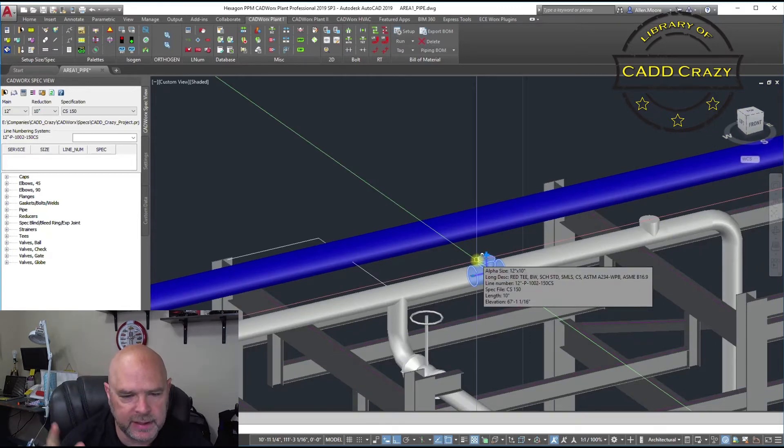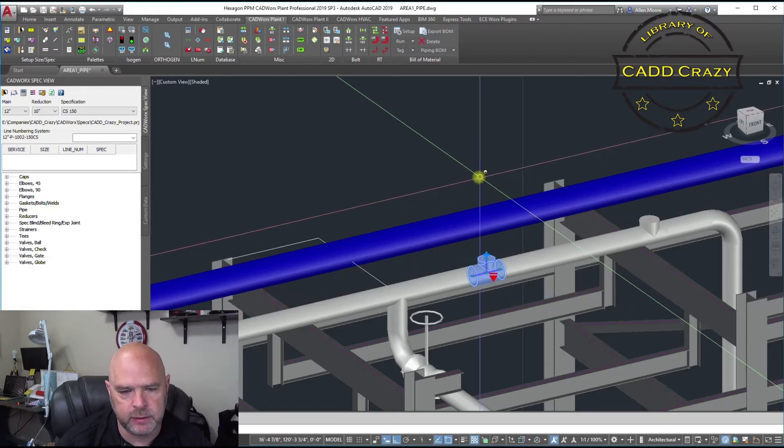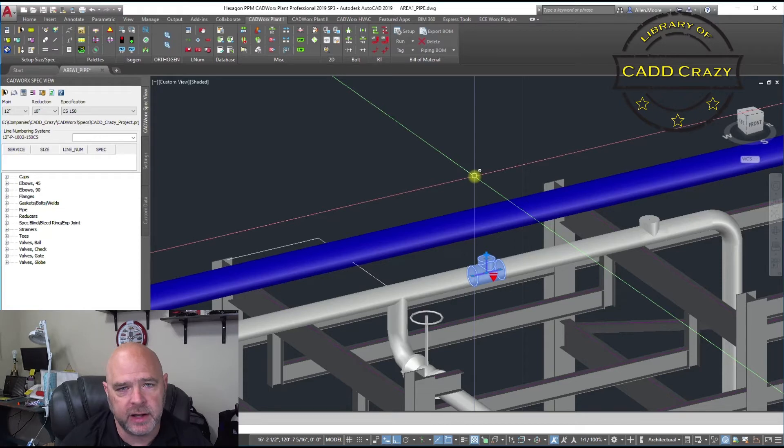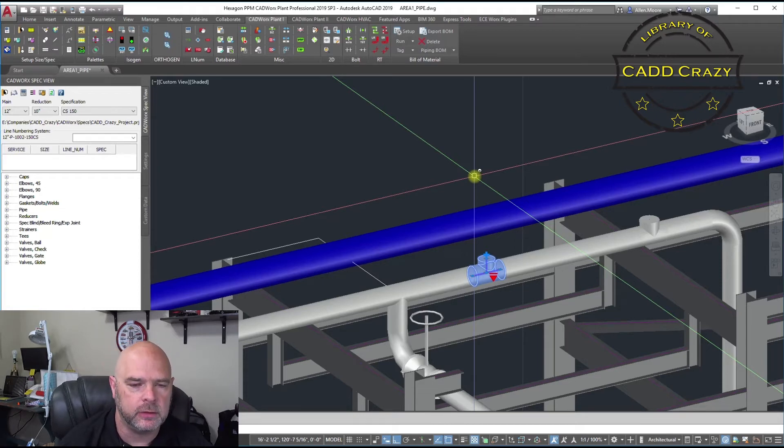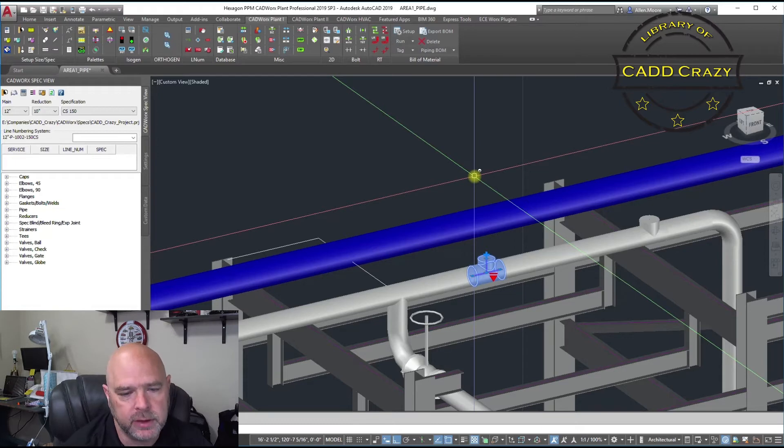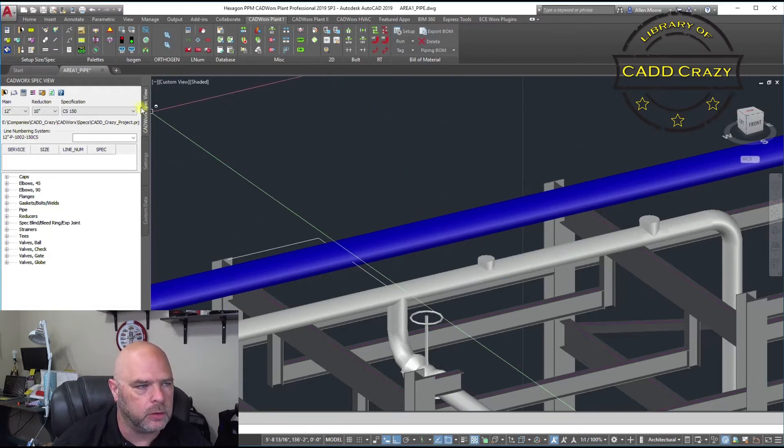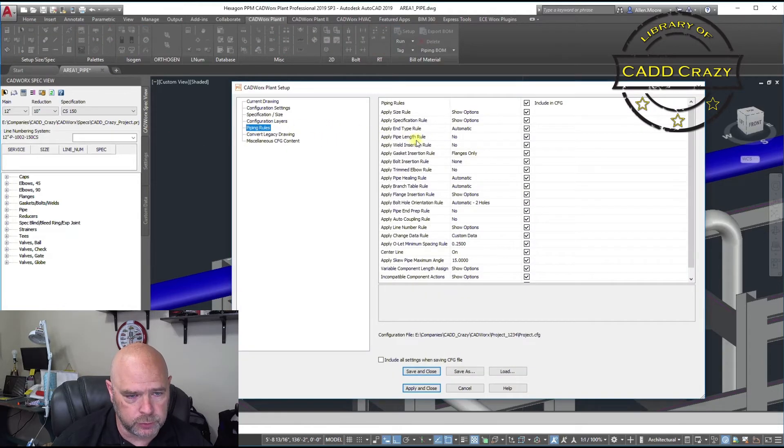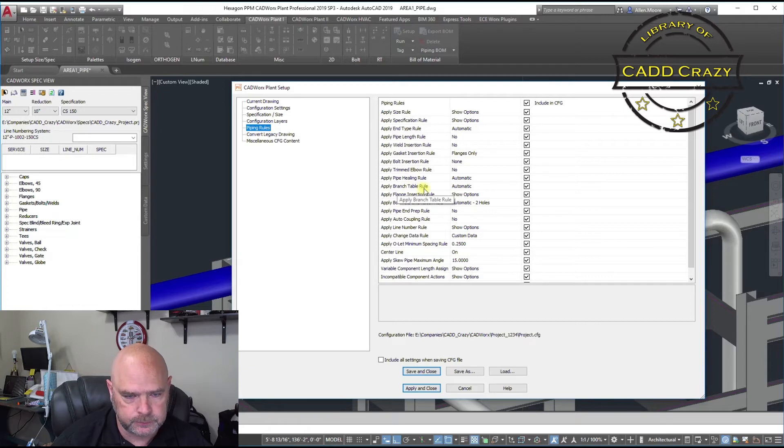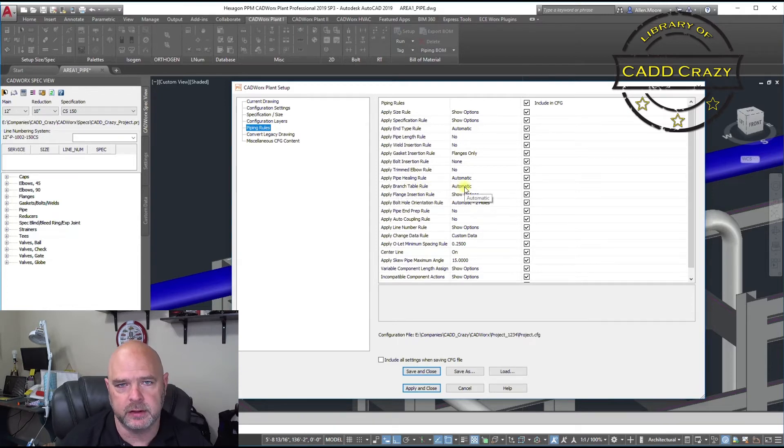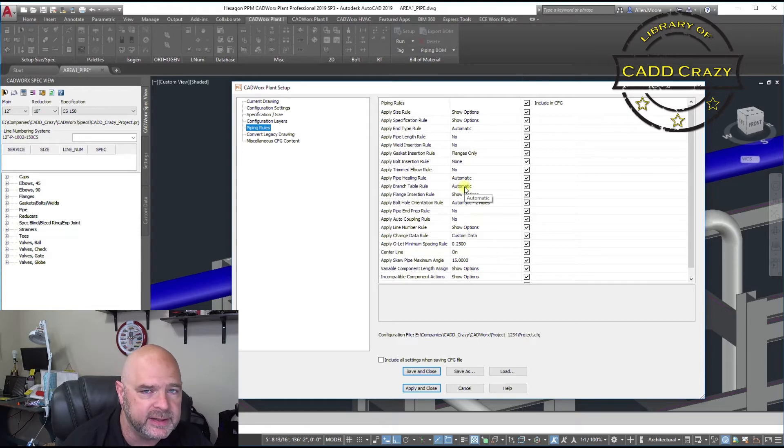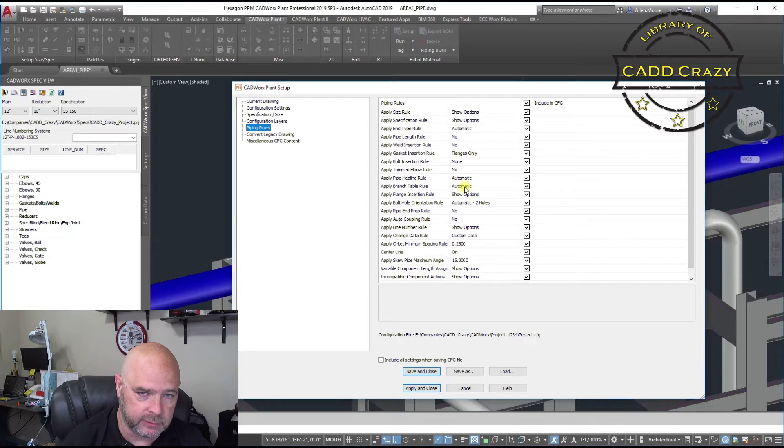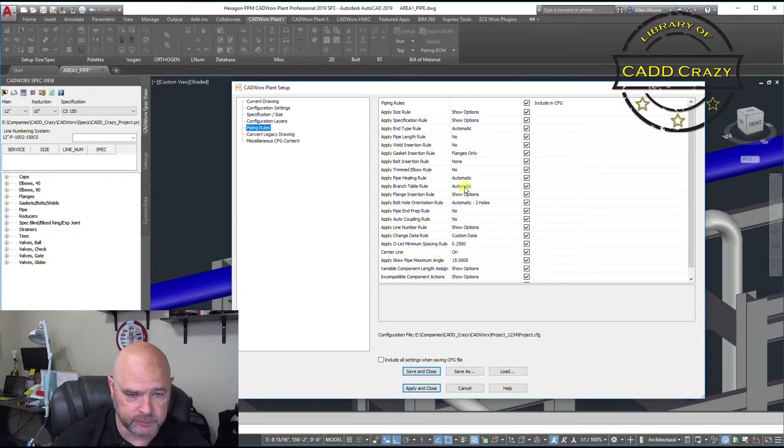Now, let's say we wanted a 12 by 8. The reason it's not giving us that option is inside your configuration or your setup on CADWorx, there's a piping rule called branch fitting. So if you go to your piping rules and come down here to branch table rule, it's set to automatic. So whatever is in your spec as what can be on that branch is what it's going to be at.